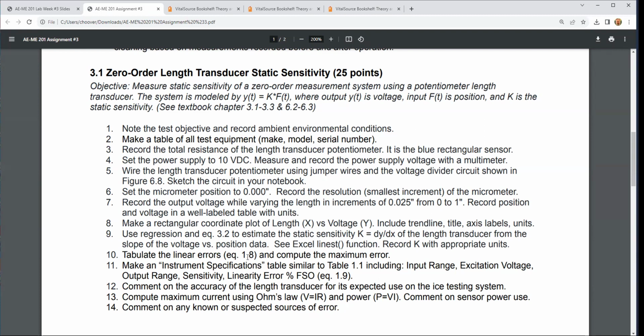Just like other instruments, you'll want to establish a specifications table, including the range, excitation voltage, output range, sensitivity, and linearity error from full scale output. Try to comment on the accuracy of the linear transducer. These are pretty good instruments, so we expect them to be very linear, and also give an estimate of the current and power used in this potentiometer.